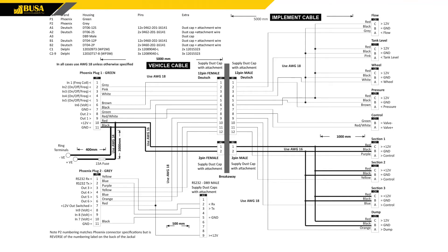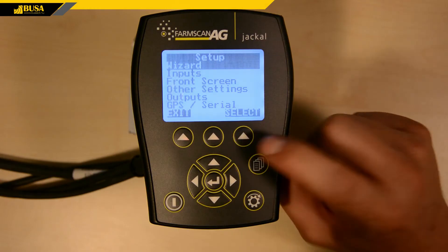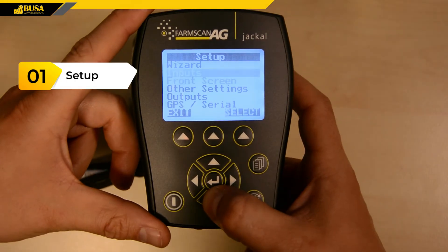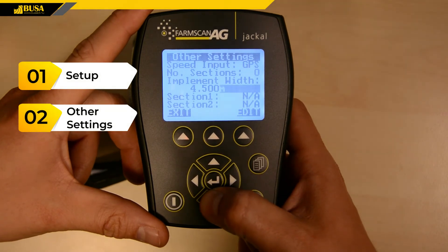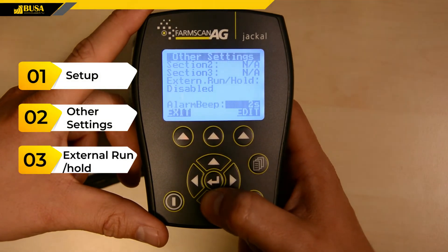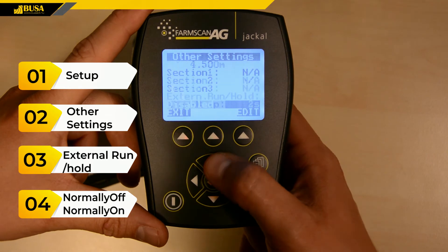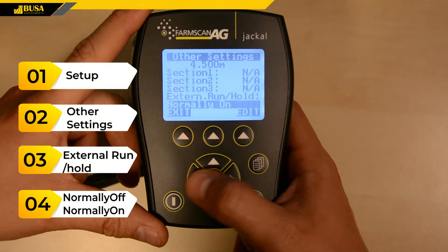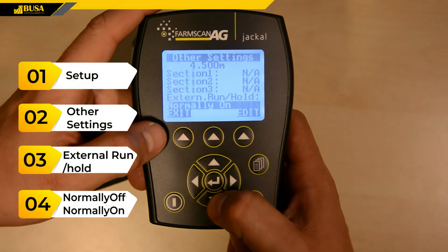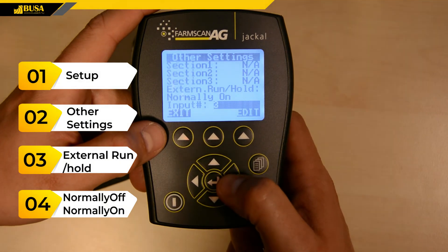If a switch is hooked up to one of the digital inputs, the controller will stop the application automatically when the machine is pulled out. We usually use input 3 with the name Tank Level. To set this up, choose the Normally Off option, or Normally On respectively, in the Setup menu Other Settings Item, under the External Run/Hold Item, then enter the number of the input.